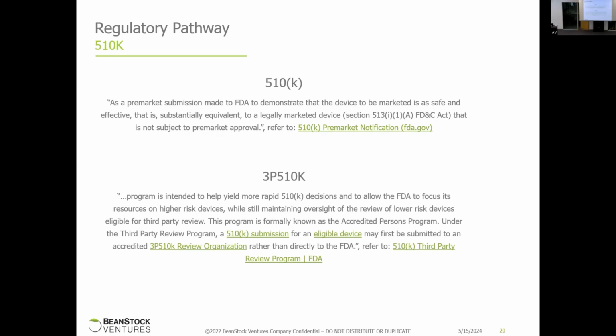510K means someone has already gone through the process of a PMA or de novo, and now there's a product code, there's a predicate. The FDA recognizes that there's an example that you can use for your submission. So this is when you actually can use a previously cleared device, and you just basically need to show equivalency. It doesn't have to be identical. You have to just show that you're equivalent. And it does not require clinical data, although you may need to submit clinical data to support your efficacy claims. It's not required.